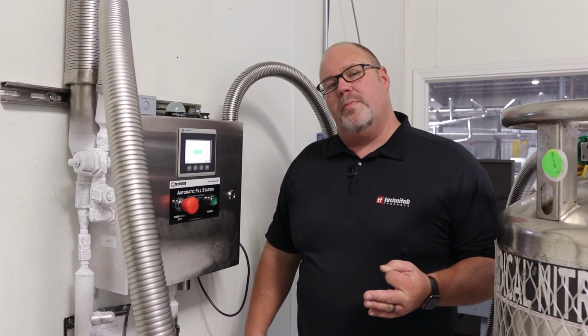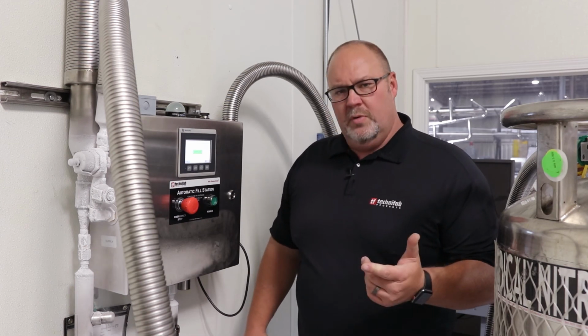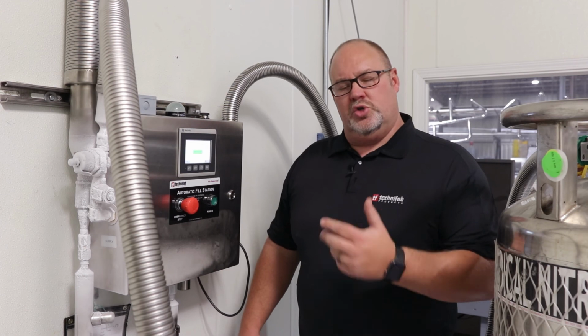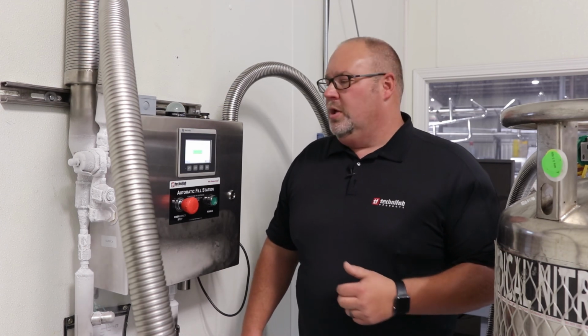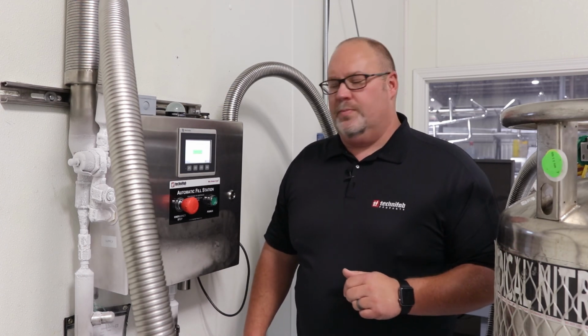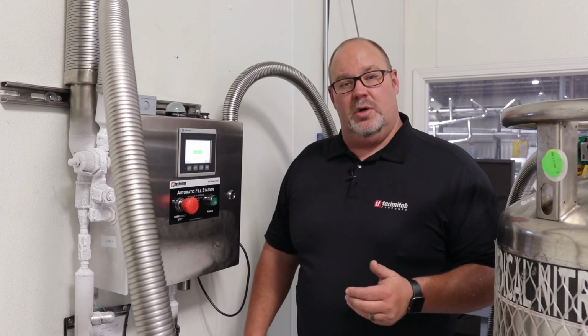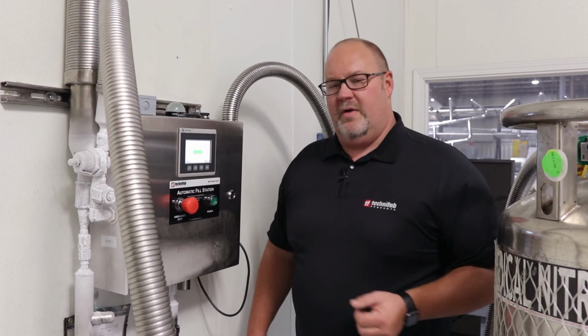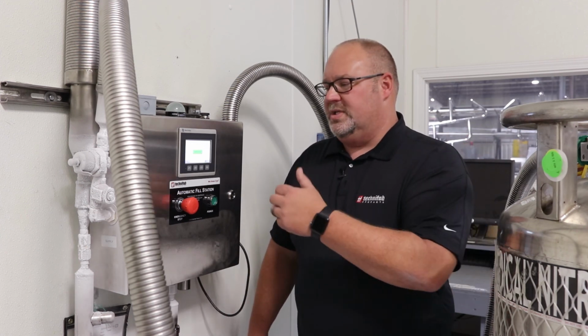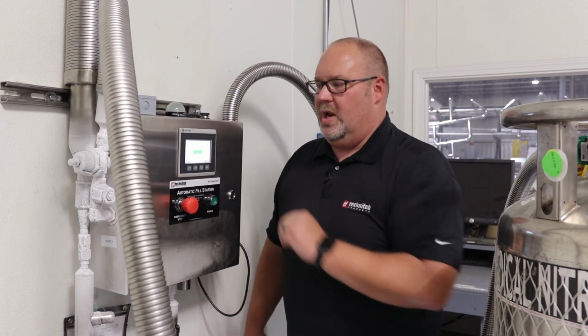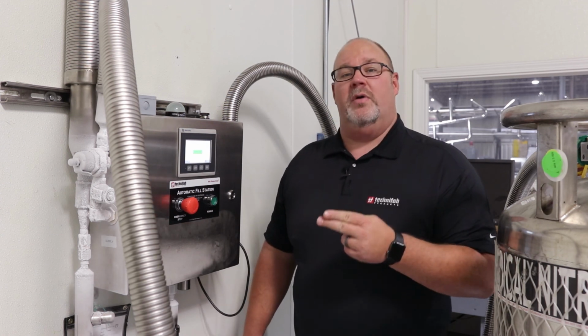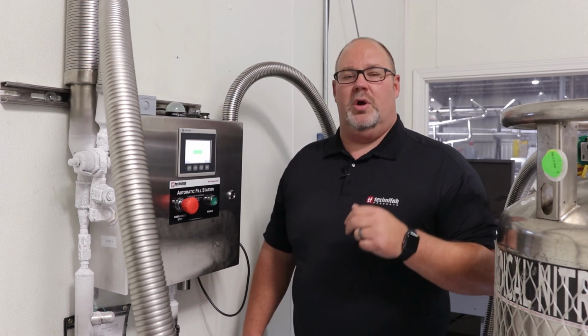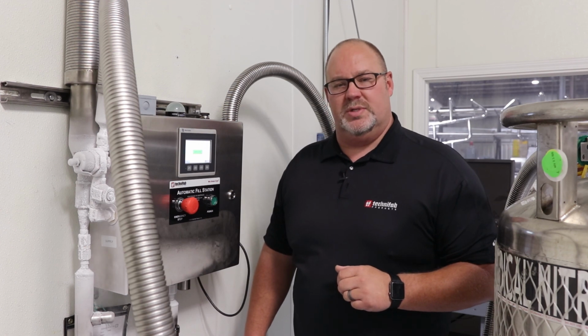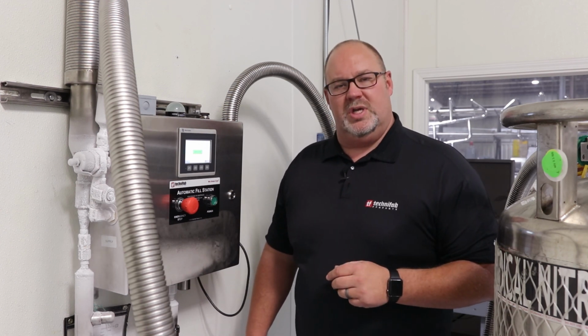You also have 3 alarm settings, which I mentioned earlier. First one is pressure transducer. So if you have an issue with your pressure transducer, you would have an alarm that would go off for that. The other one is your cryogenic sensor, which would be your temperature. If you have an issue with that sensor, you would see a different banner, but again, you would have a light and an indication that you've got an alarm issue there. And then we also have an input issue alarm, which happens if you have an issue with both the pressure and cryogenic sensors that are associated with the system. So those are your 3 alarms that you would see in this system.